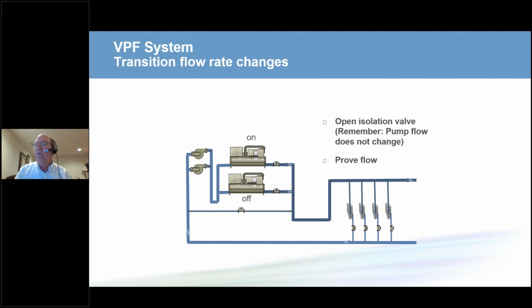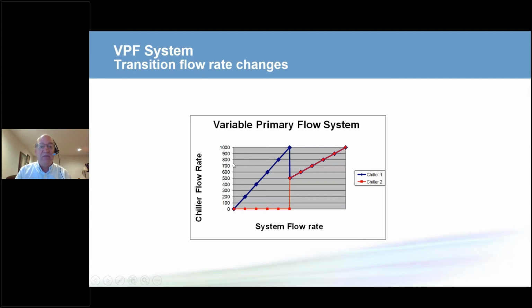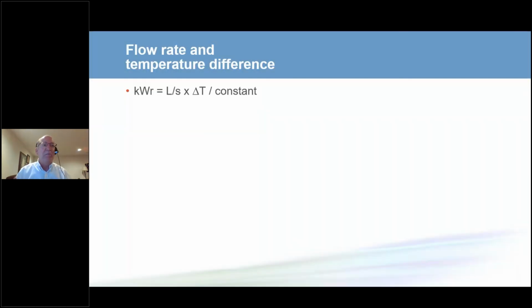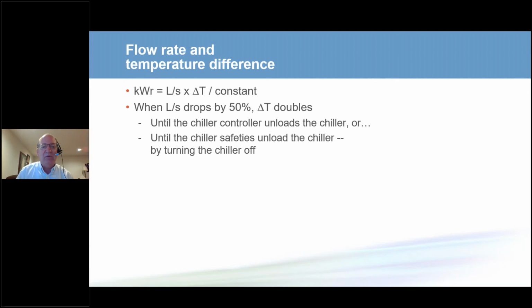But when we open this isolation valve, what happens to the flow rate through the chiller that's operating? It drops. And the question is by how much? Well, it drops by 50% if the chillers are identical. The final question is, how fast does it drop by 50%? So the capacity of the chiller is proportional to the flow rate times the delta T. We reduce the flow rate by 50%, the chiller is operating at a particular load, the delta T doubles. And depending on the conditions, it could approach freezing, but the chiller has safeties. If it approaches freezing, the chiller will cut off, it will turn the chiller off. But we don't want the chiller to turn off.